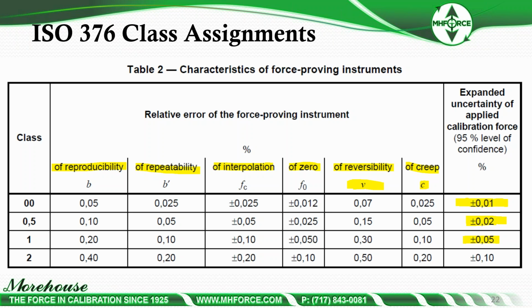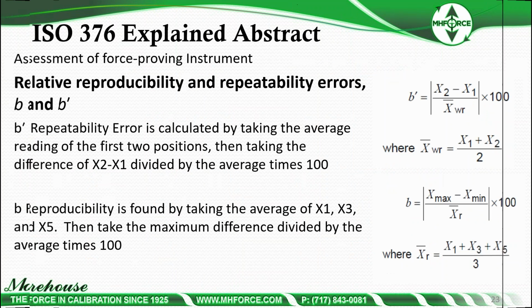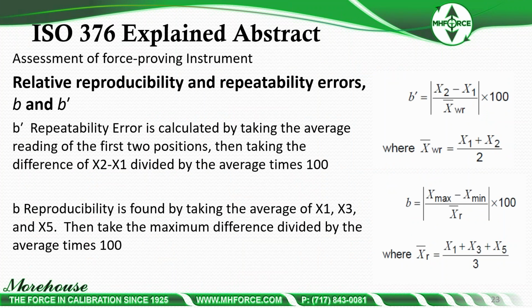And then the next, you're going to do your uncertainty, and pretty much the next calibration is going to be class half. They're going to do their calibration, and hopefully that it's going to be 1 or 2. So really nicely takes care of that measurement traceability and the metrological traceability in regards to uncertainty. This standard does a very good job with that.